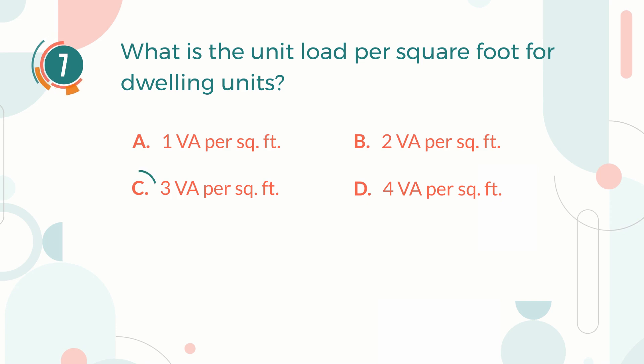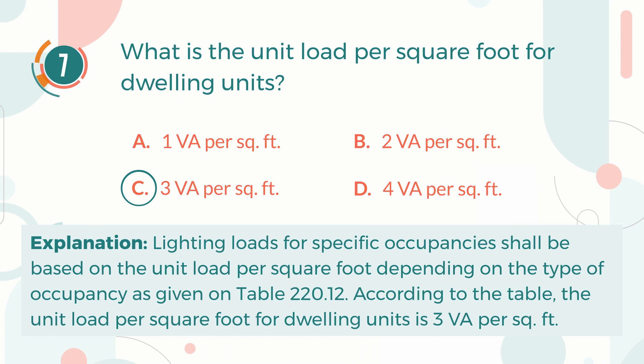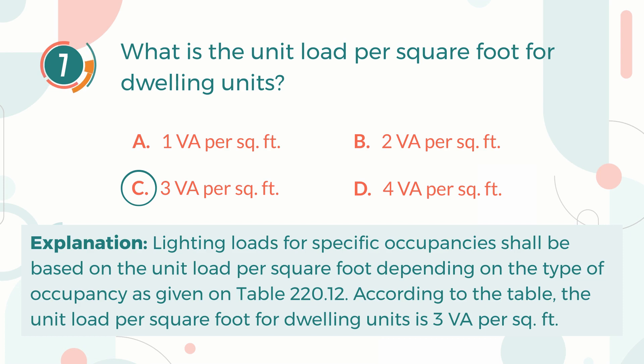The correct answer is C. 3 volt-amperes per square foot. Explanation: Lighting loads for specific occupancies shall be based on the unit load per square foot depending on the type of occupancy as given in NEC Table 220.12. According to the table, the unit load per square foot for dwelling units is 3 volt-amperes per square foot.